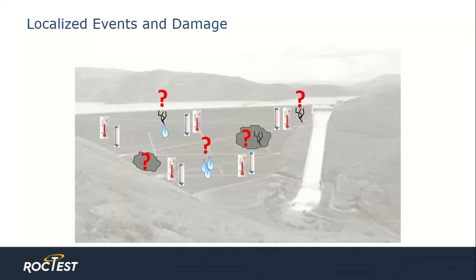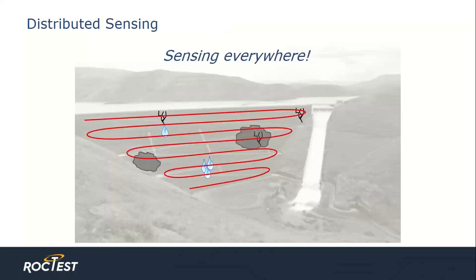Another downside to traditional sensing is cost. Adequate evaluation of a large structure such as a dam requires an extremely large number of sensors, making cost a primary concern for both materials and installation. In contrast, because the distributed cable itself is the sensor — shown here as the red line — the dam can be completely covered fairly economically. Using distributed temperature and strain sensing, we can monitor for soil deformation using the strain data and for leak detection using temperature changes, both with a spatial resolution of one meter.